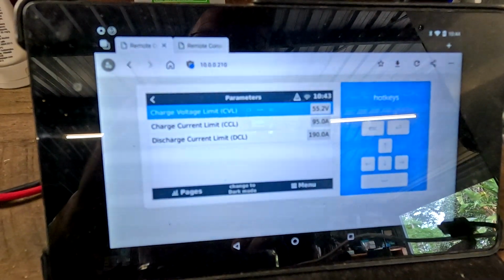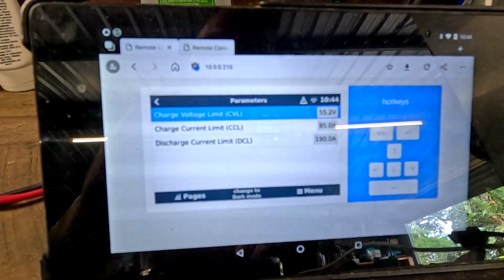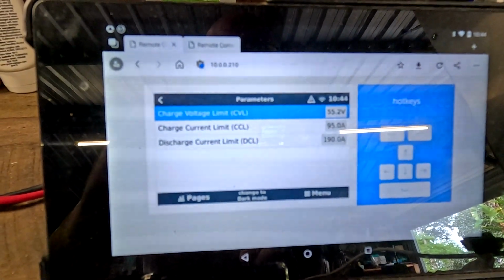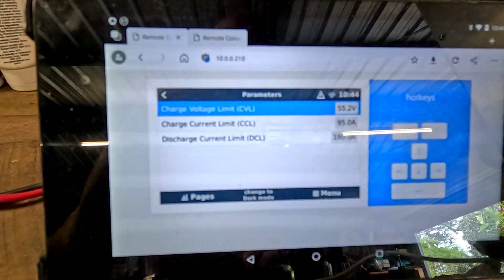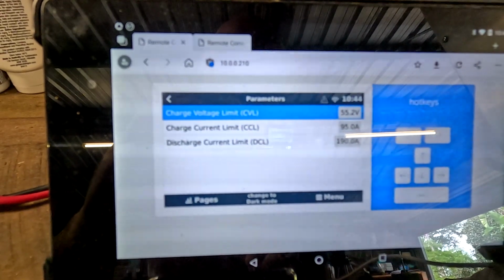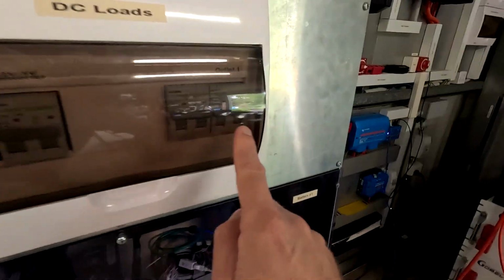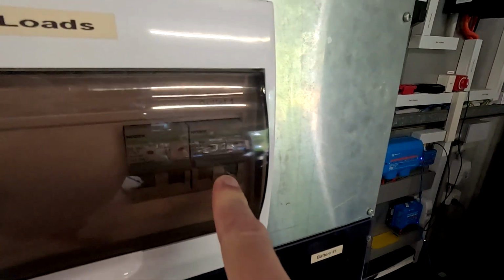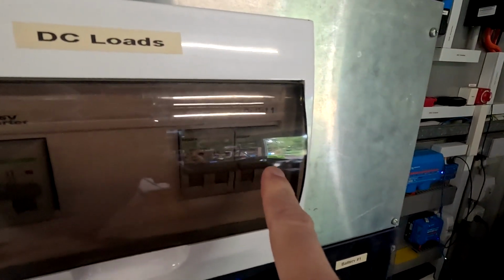Here you can see the charge parameters: 55.2 volts we are charging to, 95 amps is the maximum charge current for both batteries. We will never reach this today. We've got only a 66 amp circuit breaker, so anything over 70, 80 amps or so will trip it anyway. So I have to keep an eye on the load as well here - not charging the vehicle, not turning on the pool pump at the moment, just keeping it a bit shallow with the load, so these two batteries, or better my circuit breaker here, can actually cope.